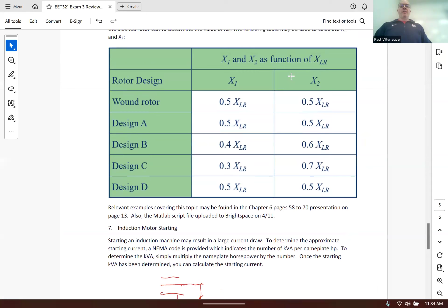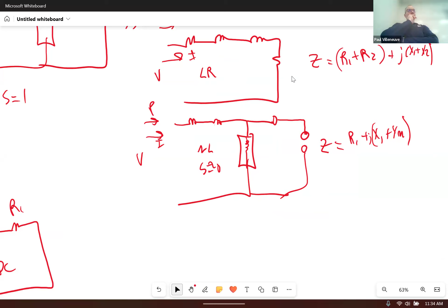you know the current through the circuit for each condition. Right? Yeah, you've got to measure that. It's a test, so you have to measure those parameters. So you measure V, I, and P. In this condition you get this much current, and in this condition you get this much current, and then you can calculate the resistances R1, R2. And then you have to use the NEMA design for that table to calculate X1. This one is going to give you X1 plus XM. This one is going to give you X1, X2. So you'd use a table over here.